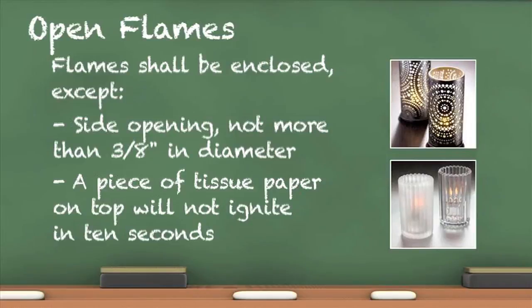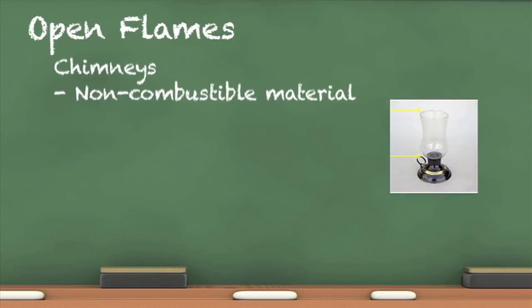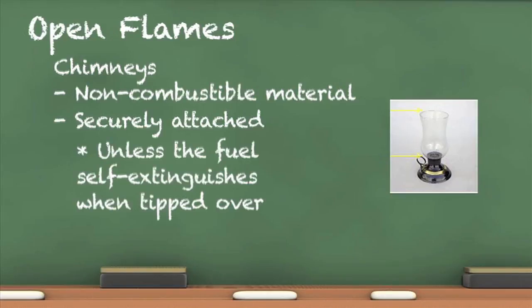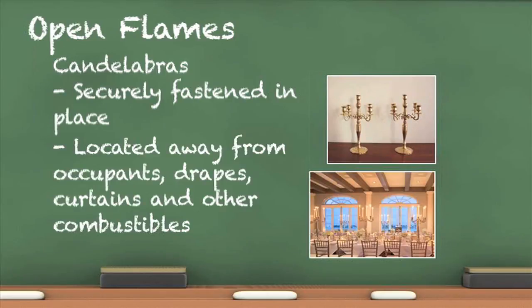Open flames must be enclosed; however, it is permissible to have openings on the side provided they are no more than three-eighths of an inch in diameter. The top distance to the flame shall be such that a piece of tissue paper placed on top will not ignite in 10 seconds. Chimneys — the decorative open flame cover — are required to be constructed of non-combustible material and securely attached to the open flame device. The chimney is not required to be attached if the fuel self-extinguishes when tipped over. Candelabras with flame-lighted candles shall be securely fastened in place to prevent overturning and located away from nearby occupants, drapes, curtains, and other combustibles.